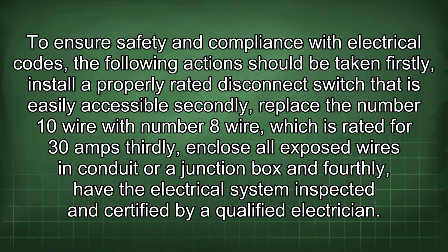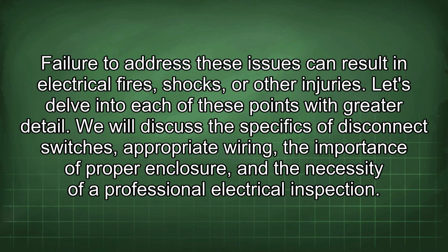To ensure safety and compliance with electrical codes, the following actions should be taken. Firstly, install a properly rated disconnect switch that is easily accessible. Secondly, replace the number 10 wire with number 8 wire, which is rated for 30 amps. Thirdly, enclose all exposed wires in conduit or a junction box. And fourthly, have the electrical system inspected and certified by a qualified electrician. Failure to address these issues can result in electrical fires, shocks, or other injuries.